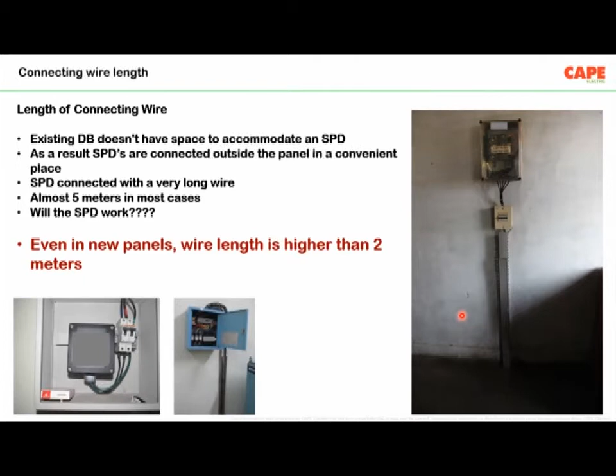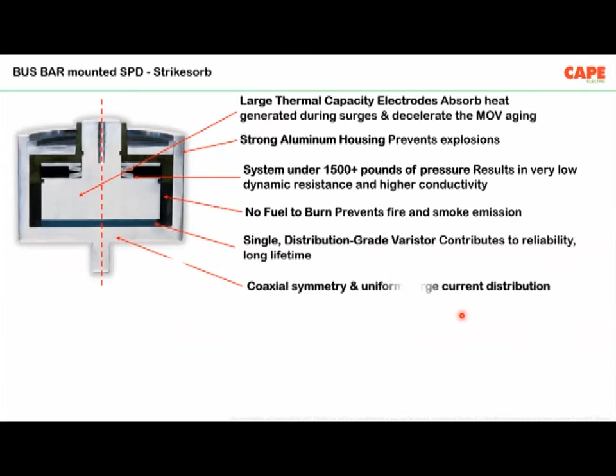But unfortunately, if we look at 100 electrical SPD installations in our country, almost 80 SPDs are installed in this fashion. The wire length recommended is 250 millimeter, but more than 2 meters are used. As a result, in most cases, SPDs are just decorative. It won't work. For this particular purpose, you must use special SPDs like the bus bar mounted SPDs. The advantage of these bus bar mounted SPDs is you are directly mounting on the bus bar. As a result, the voltage drop due to line length has been nullified. There is no line length applicable.